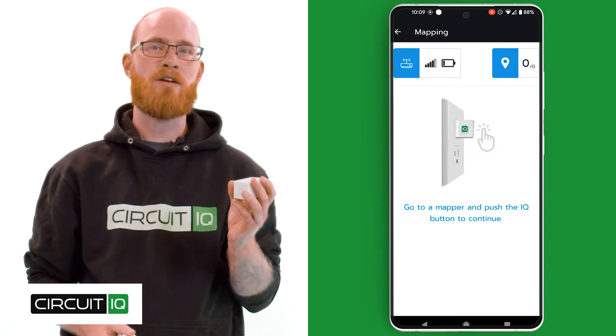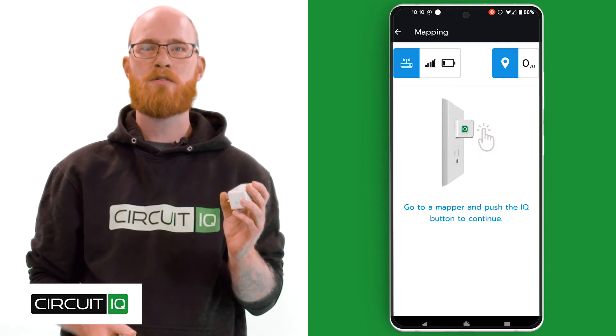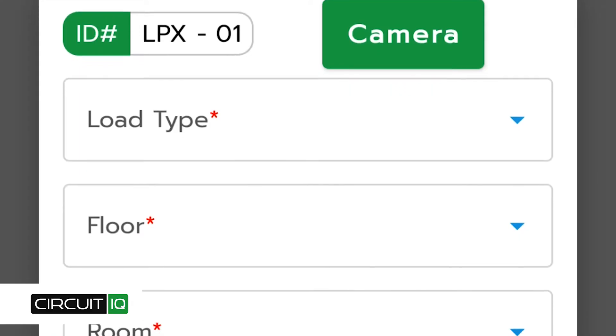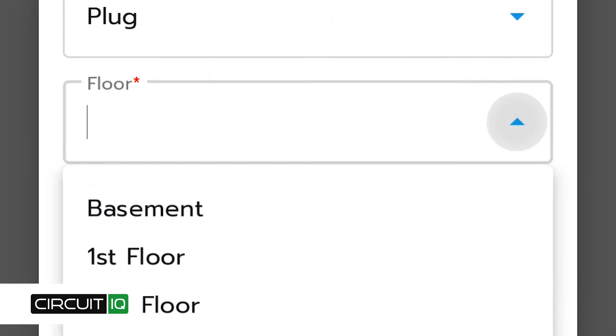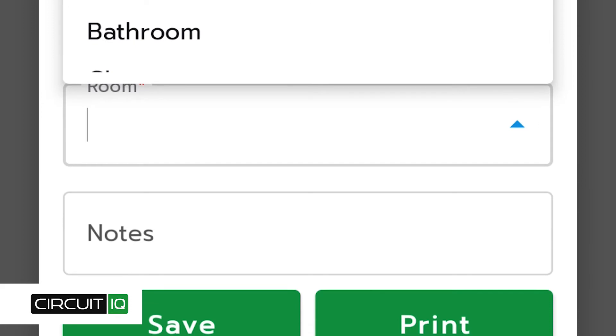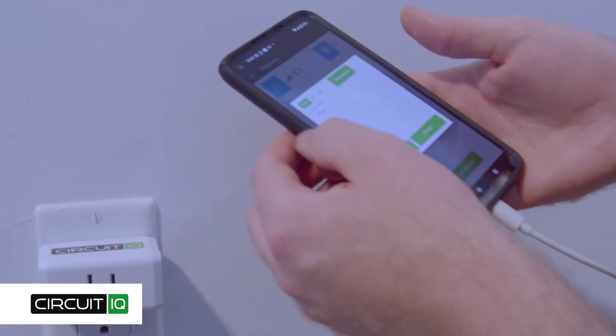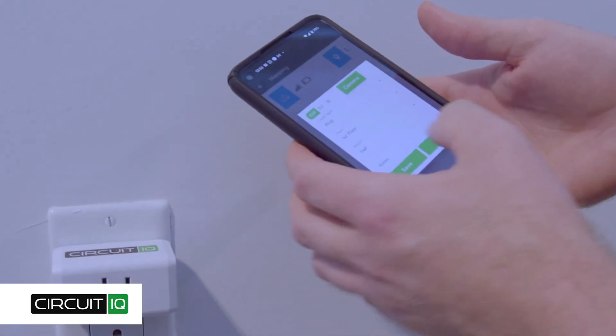Click the IQ button on the side of the CircuitIQ mapper and enter the device details on your smartphone. This includes the type of load, the location, and any notes to include such as AFCI. If the app tells you this outlet was not mapped, it means the breaker wasn't cycled — this could be because of hidden sub-panels or a circuit breaker that wasn't turned off. Continue this process for every mapper until each one has been identified and collected.